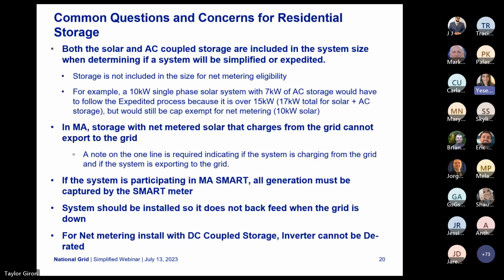Some common questions and concerns for residential storage. Both the solar and AC coupled storage are included in the system size. This goes back to my very first slide where I mentioned to put in the correct system size at triage. Storage is not included in the size for net metering eligibility. So if you have a 5 kW inverter, 5 kW Tesla, it equals 10 kW AC. However, it'll still fall under net metering because your inverter is 5.